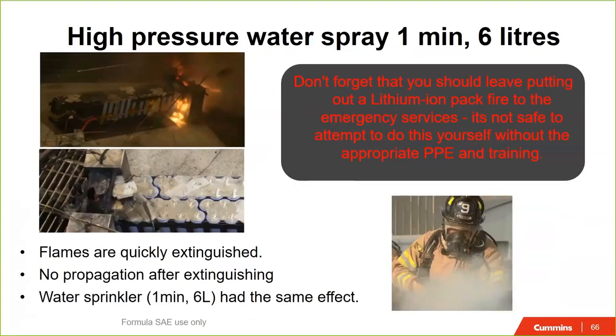The best way to put out a lithium-ion fire is using high-pressure water, and lots of it. We talk in terms of the combustion triangle: to have a fire you need heat, fuel, and oxygen. If you remove any one of those, the fire will extinguish. The only thing we can remove in a lithium-ion fire is heat, and the best way to do that is water, and lots of it.